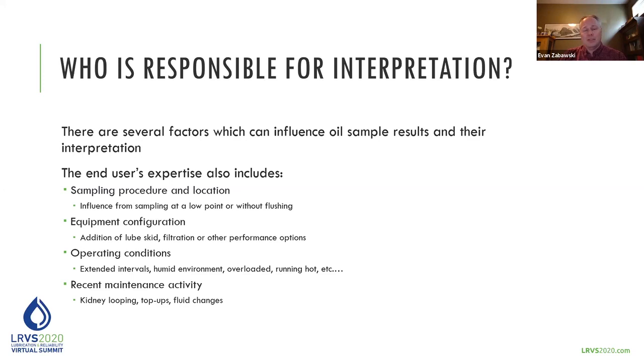End users should know too the operating conditions, right? They might expect a sample to come back with high water content or some contamination just because of the environment that it's working in. And again, they may know things that are going on within the equipment or within the operation of the equipment to guide why the result has gone in the direction it has. And the last thing I'll point out is that they also know if they've done anything to it. Right? When an oil analysis lab sees the result get significantly better than a previous result, we're left with basically an assumption the oil has been changed. But you might know that you've added in filtration or some other remediation technology, and you've made it better somehow.